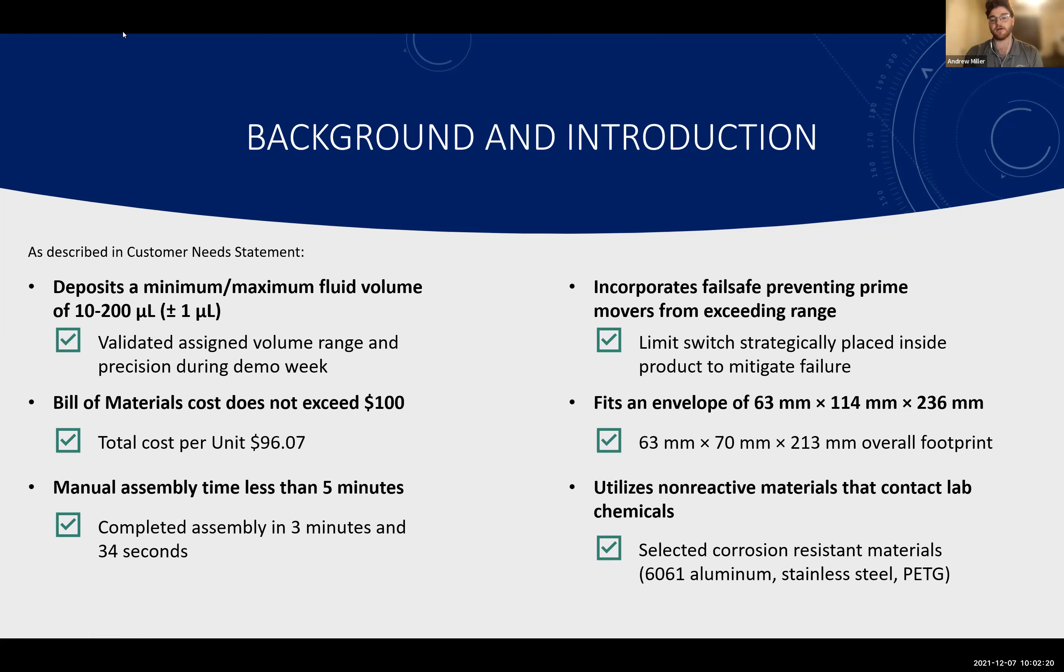Since this microbioreactor is asked to operate for up to two weeks at a time with no human intervention, we placed a limit switch at the bottom of our design to incorporate that fail-safe that was asked. Noting on the modularity of the microbioreactor again, it was asked to be in that certain volume envelope, which our design does. And lastly, since this will be in the lab setting, we incorporated non-reactive metals and plastic in our design.